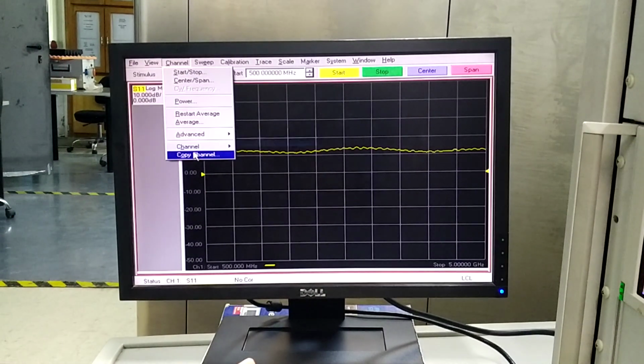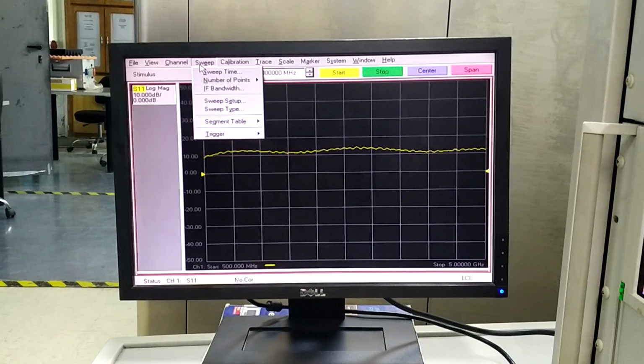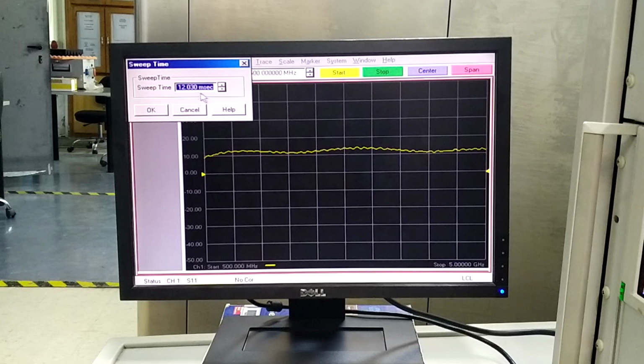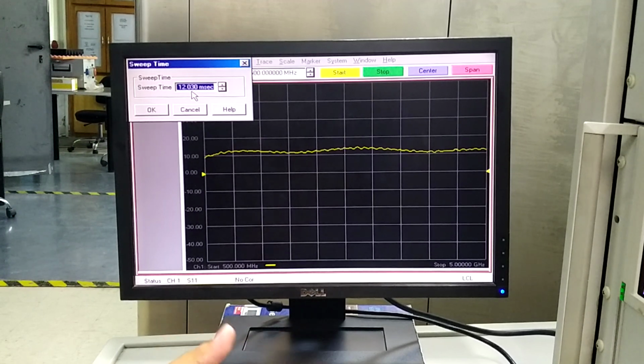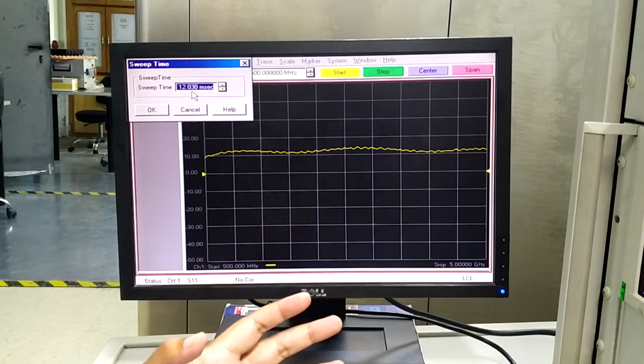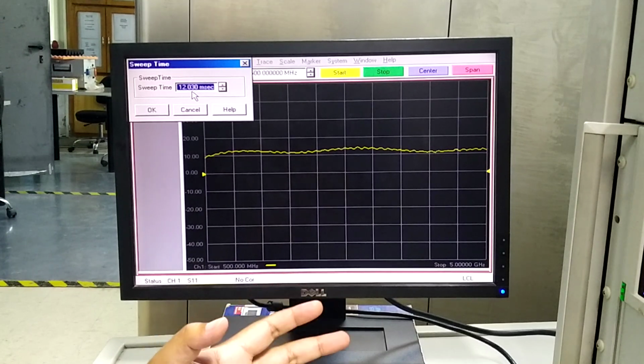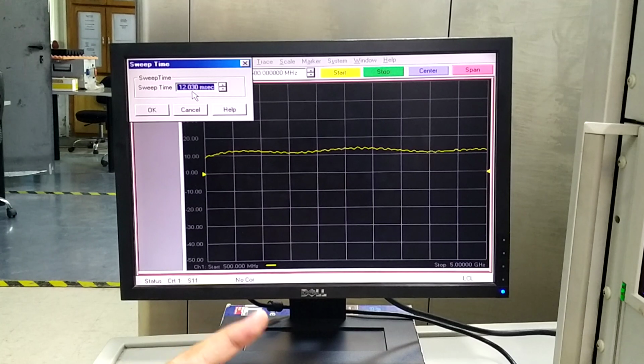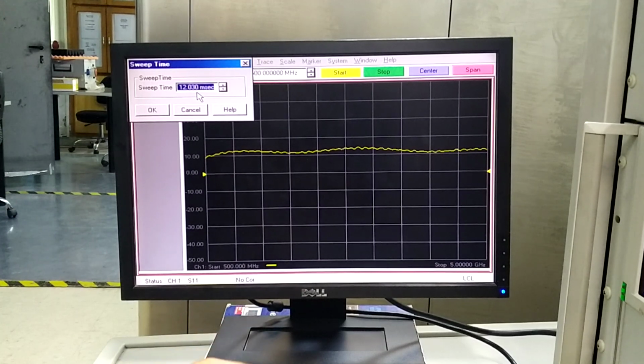Now there are also advanced options. We will leave them like this for this lab. Then we go to the sweep tab, and here you can see the sweep time. The sweep time is very important, and it is generated by the VNA. So what is the sweep time? Sweep time is the time required by the VNA to complete the operation. For example, start from the starting frequency of, let's say, 500 megahertz and go to the stop frequency of 5 gigahertz. The time it takes to do the measurements from 500 megahertz to 5 gigahertz is known as the sweep time, and here it is automatically shown as 12.030 milliseconds.